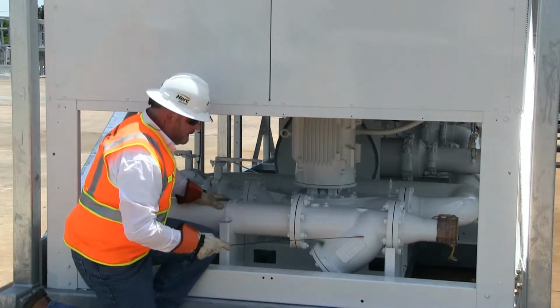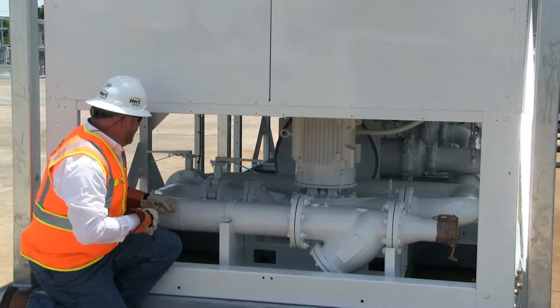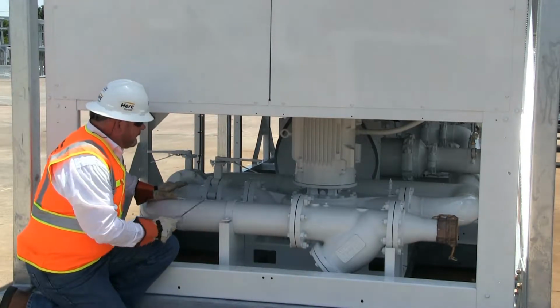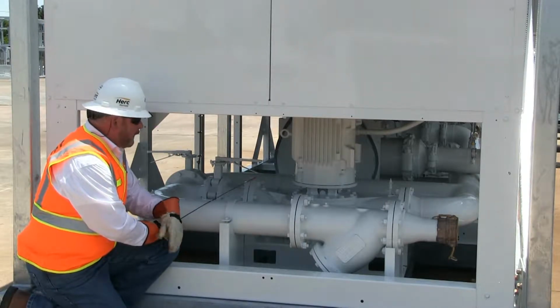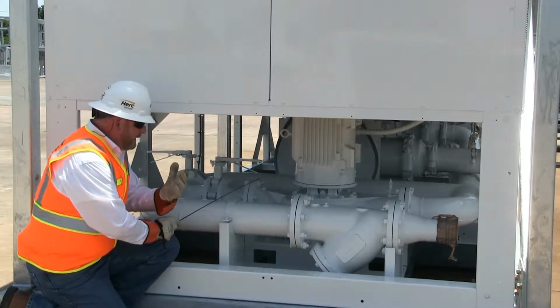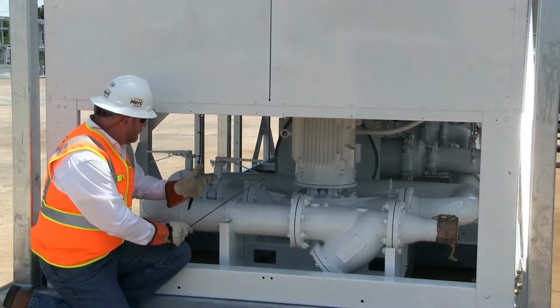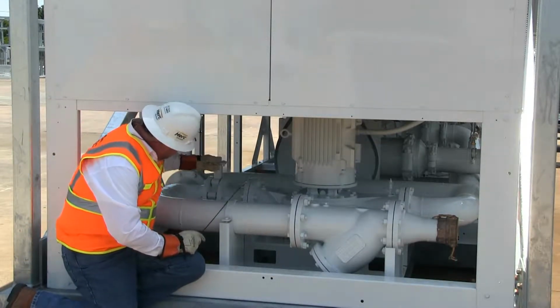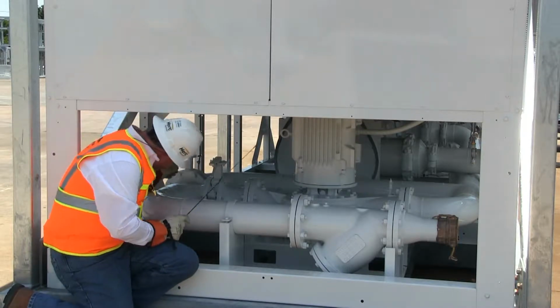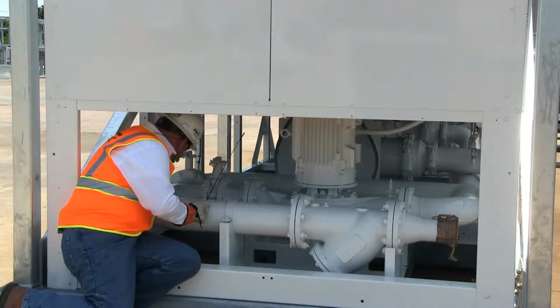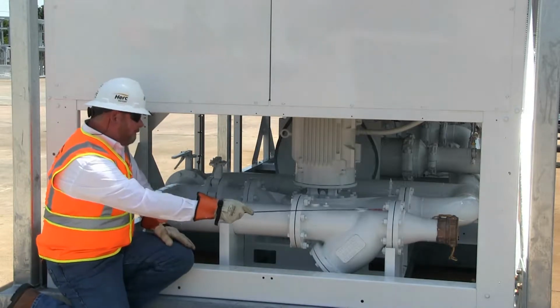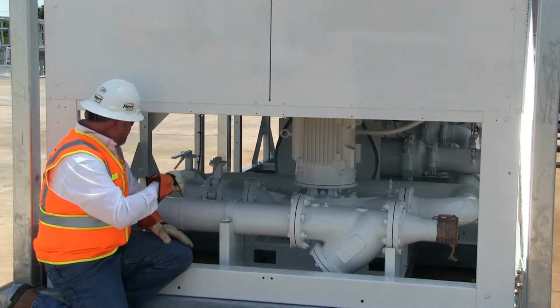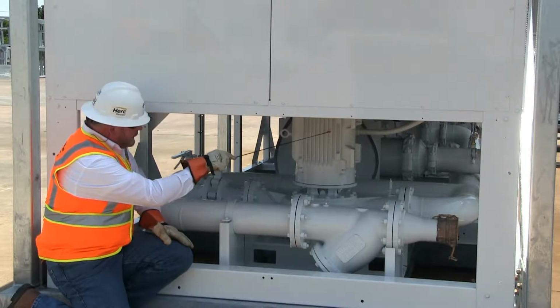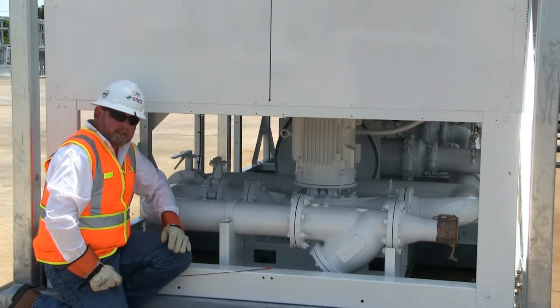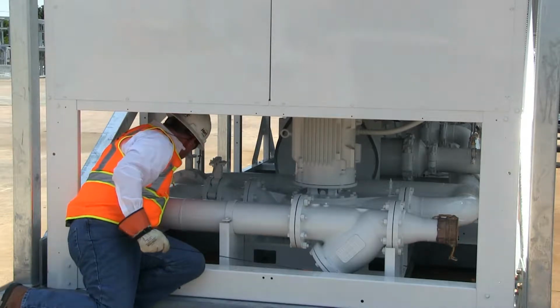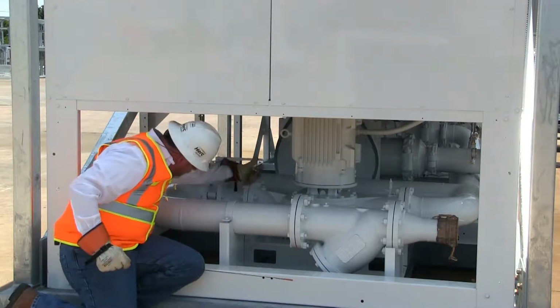So as our flow comes in here, goes through the strainer, comes out, then we've got to make a decision here. Since we have an integrated pump here, we can operate the machine off our pump, but if our customer has their own pump and doesn't want to use our pump, it's very simple. It's just a matter of closing the inlet valve going into our pump, and then we're going to open the valve going into our bypass there. So now the water flow will come in. It won't go through the pump, but it will bypass the pump and go through the heat exchanger. If we're going to use the pump in an installation, we just simply reverse that by closing the bypass and opening up the pump valve there.